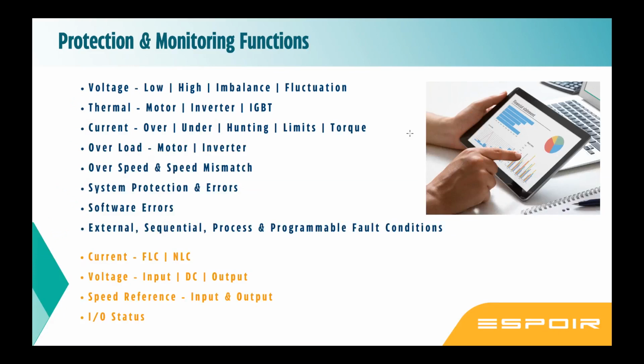Now let's come to protection and monitoring functions. What protections does a standard VFD give? It protects the system from low voltage, high voltage, voltage imbalance, voltage fluctuations. All this it trips: under voltage, over voltage, imbalance, voltage fluctuation. Imbalance is within three phases, two phases are 400, another phase to phase is like 280, 300, 340. That is the imbalance. Fluctuation is when it is fluctuating between 300 to 400. There are certain tolerances given. So if it is fluctuating beyond that tolerance, it trips. You cannot disable this aspect.